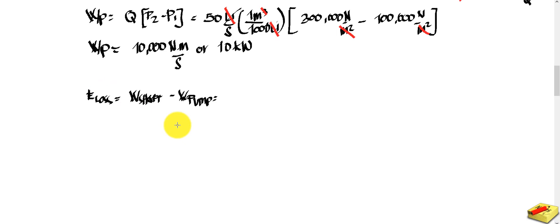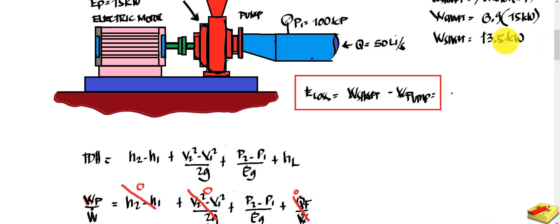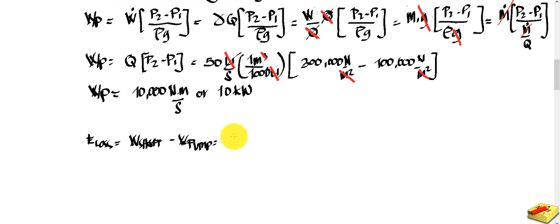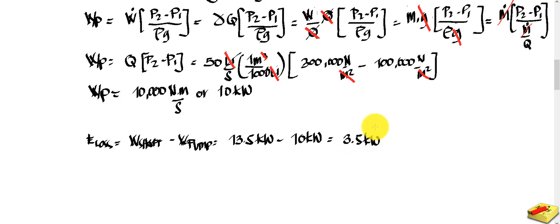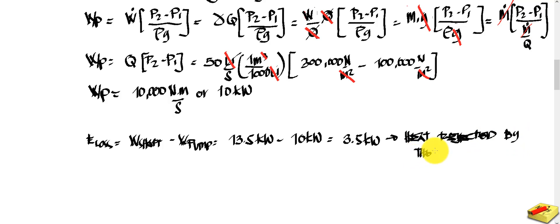Substituting the values: E_loss equals work of the shaft minus water horsepower, so that is 13.5 kilowatt minus 10 kilowatt, giving E_loss equal to 3.5 kilowatt. This is the heat being rejected to the system due to inefficiency and friction.